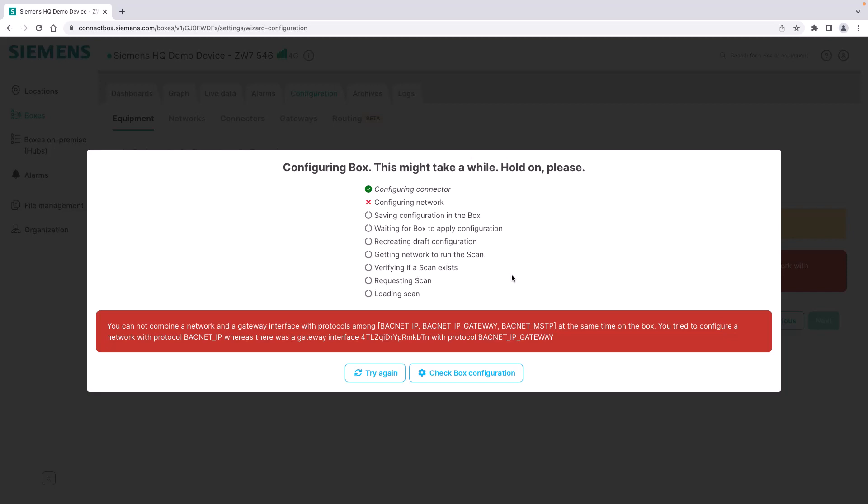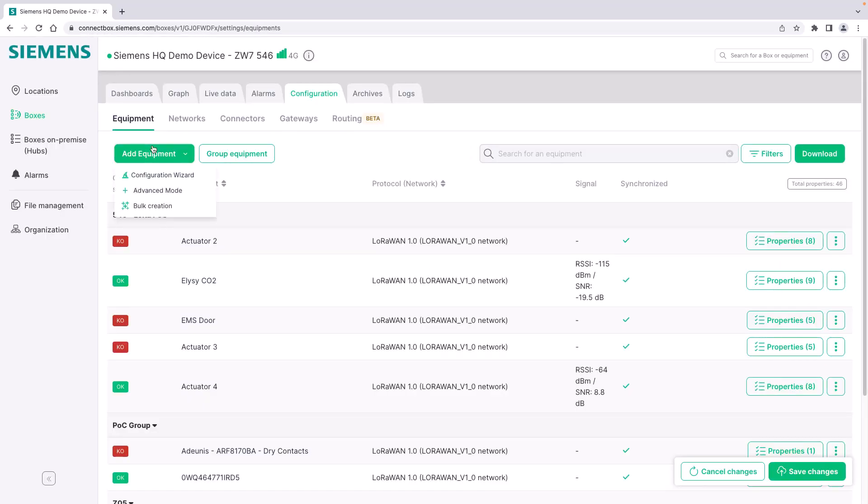This scan resulted in an error because I'm already using this box as a gateway northbound in order to expose BACnet objects on the network. It cannot act as a southbound BACnet protocol gateway and I first have to remove my BACnet IP gateway. You can go on with the scan and you will be able to detect BACnet objects on the network. I will show you in another video how that works.